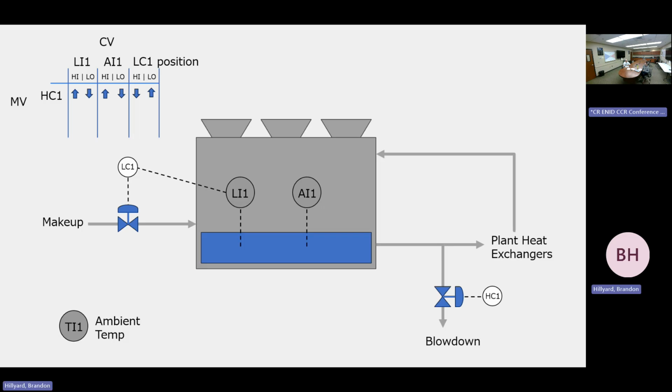And then, yeah, temperature feed forward. As the ambient temperature goes up, your evaporation rate is going to increase, which is going to increase your conductivity. And so you're going to need to increase your blowdown to account for that.